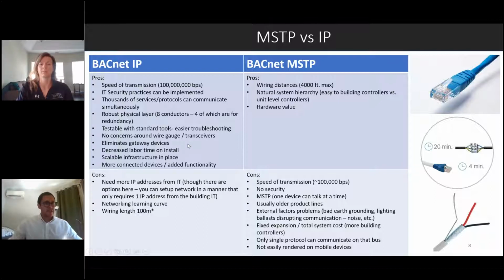Fewer gateway devices as you move into the IP protocol, and it's just a really good, scalable infrastructure. So it's very helpful to install along this with BACnet IP. I personally think that's the way to go for any new buildings. You should be looking at IP. The controls contractors and controls manufacturers that do it right can really bring together a lot of awesome features with their IP product line that just aren't available with MSTP products. Stephanie was pointing out RESTful API — you can't do that over MSTP communication. So we're starting to leverage all these interesting technologies as we move forward.